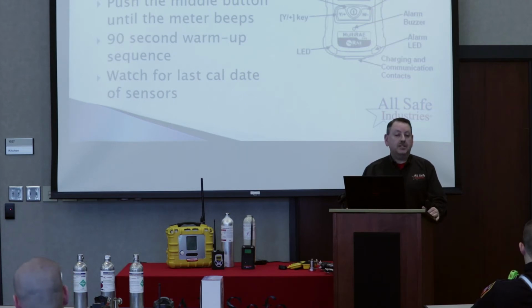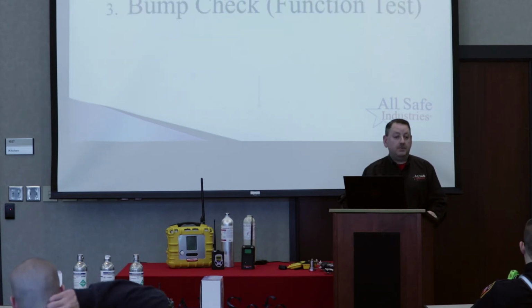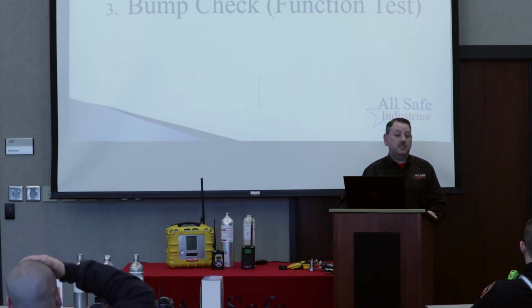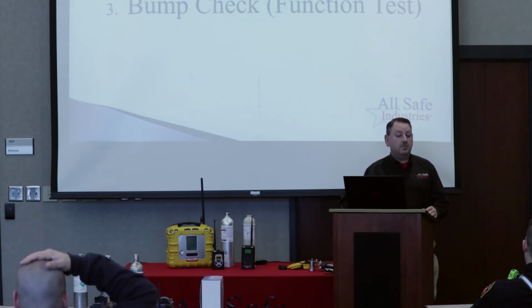Other than that, you guys are going to get comfortable enough with this meter where you'll turn it on and then you'll set it to the side while it does its warm-up, go get some other equipment ready, and then come back to the meter at the end. Because at the end of the warm-up sequence, it's going to ask if you want to do a fresh air calibration, which is going to kick you off into these 3 steps, okay? So I'm going to explain these 3 steps.